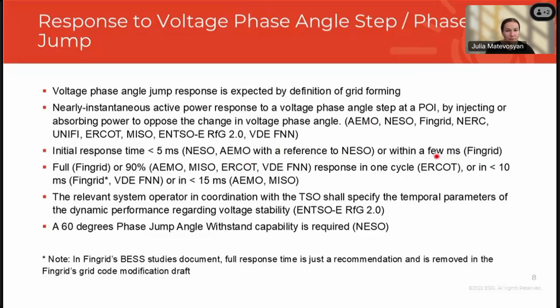FinGrid says within a few milliseconds. And then FinGrid requires full response, while others specify 90% of response in a certain time. So ERCOT says 1 cycle, FinGrid and VDE say 10 milliseconds, and AEMO and MISO specify 15 milliseconds. So this is to full or 90% response.